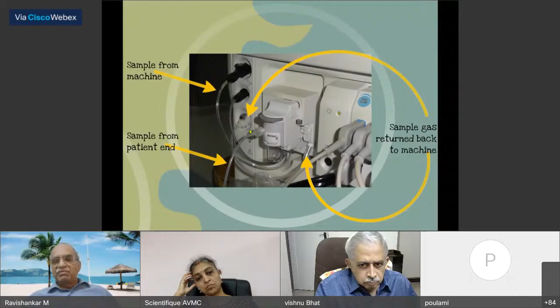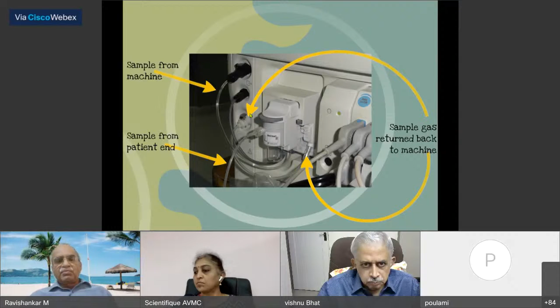And here the monitors that we use for monitoring gas concentrations do the sampling from the patient end, and it goes inside. After analyzing all that, the gas that is emitted out is taken back and recirculated into the machine so that it is not spilling over into the atmosphere. This is one of the advances that have been made, so that even that minimal, about 100 ml of gas that is taken out for analysis, is not put into the atmosphere but is put back into the machine.